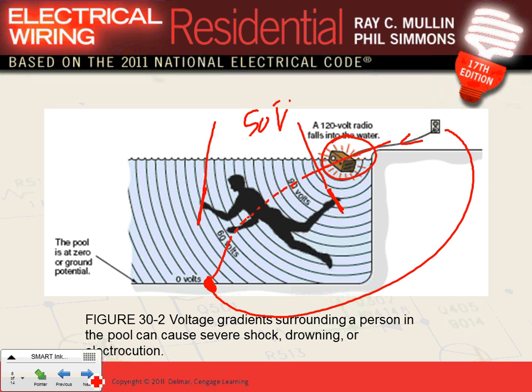It's like lightning, very similar to lightning, guys. You could be standing and the lightning hits the ground and the current goes from one foot to another and you get burned. High voltage is notoriously famous for that. That's called the gradient. So that's the same thing. You're going to have a voltage difference between 2 points on that object and basically get electrocuted.